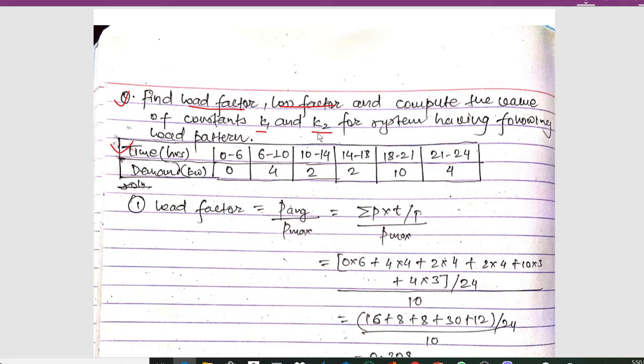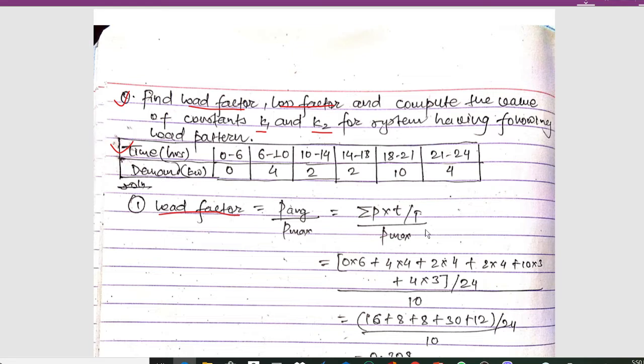We have to determine the load factor, loss factor, and constants k1 and k2. The formula for load factor is: load factor = P_average / P_max, where P_average = summation(P × t) / T / P_max. So summation P × t gives us: 0×6 + 4×4 + 2×4 + 2×4 + 10×3 + 4×3, divided by T = 24, and P_max is 10 kilowatt.